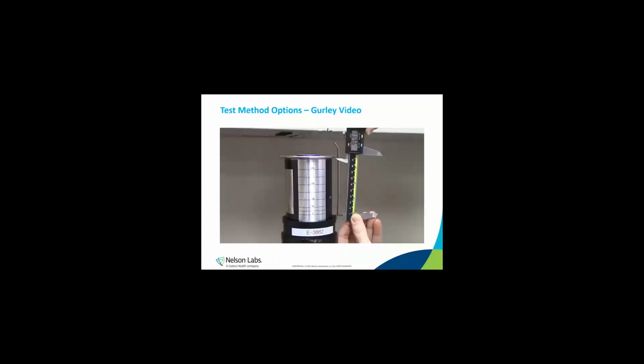And if the difference between the 2 measurements is less than 1 millimeter, then the sample passes. If it's greater than that, then that probably means that either we didn't do a good job measuring, or the sample had a slight porosity to it and the cylinder dropped a little bit.